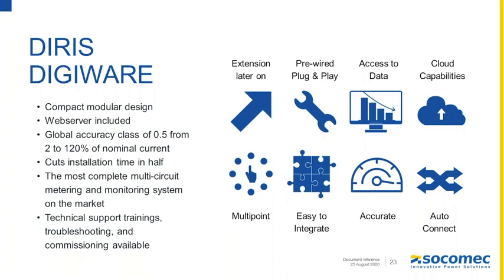The global accuracy is class 0.5, meaning 0.5% accuracy. The Diris DigiWare can also be expanded simply by adding current modules and current sensors to the existing system. Every time you want to expand the performance of your power monitoring system, you don't need to start over with a complete new system — it's only add-ons, and they are plug and play.